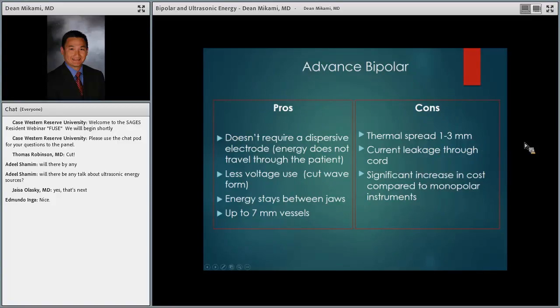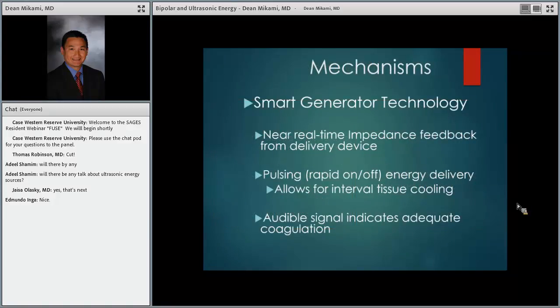The cons are we do have thermal spread that we see with the advanced bipolar devices, 1 to 3 millimeters in size. You do have current leakage through the cord, so don't wrap your bipolar cords or your monopolar cords around hemostats and then place the hemostat over a pacemaker. That's going to affect that. And definitely a significant increase in cost compared to other monopolar instruments. This is the mechanism I talked to you about, the advanced bipolar units now. It has a near real-time impedance feedback, or resistance feedback, from the tip. You get this pulsing, rapid on and off energy that's being sent out. It allows for interval tissue cooling, and you get an audible signal that indicates an adequate seal. So basically a delta change in resistance, and it has your beep.